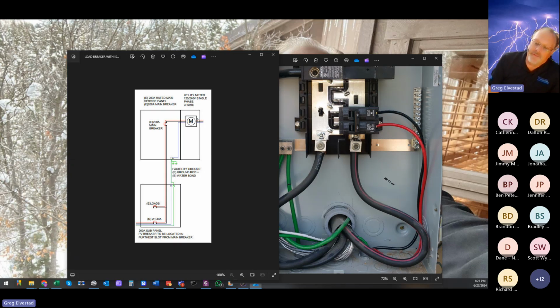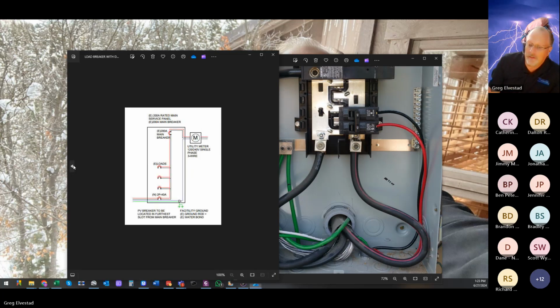Sub panel off of a feeder, just the same 120% rule, fed off of the sub panel. Maybe the sub panel is convenient to get to. If it's on the opposite side of the house from the service, and that's where you want to connect your PV, you can punch through the wall and land on that sub panel. Another example, just the same thing.